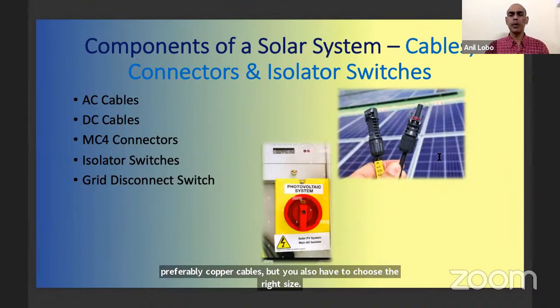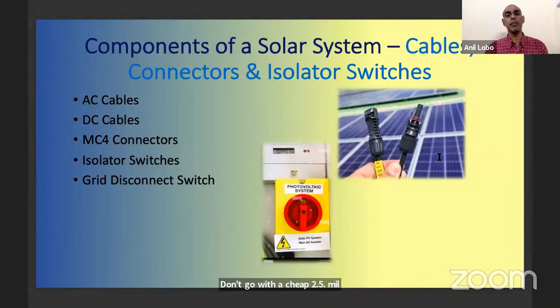Don't go with a cheap 2.5 milli cable when a 4 milli cable is suitable, and don't stay with the 4 milli cable when you need to go higher, like a 6 milli or even up to 10 milli. It is better to design on a higher DC cable rather than lower. Most AC cables, especially in the domestic circuit, will be no more than 4 milli, typically 2.5, and you can go as low as 1.5 without affecting the integrity of your system. But if you go wrong with your DC cable, not only will it overheat, there is a safety aspect of catching fire.